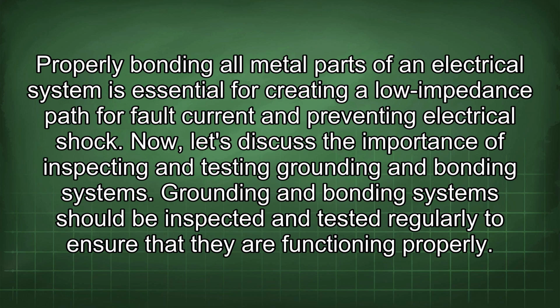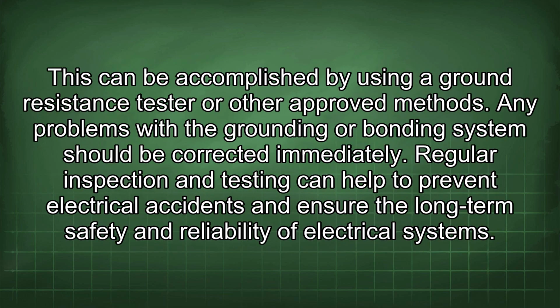Properly bonding all metal parts of an electrical system is essential for creating a low impedance path for fault current and preventing electrical shock. Now let's discuss the importance of inspecting and testing grounding and bonding systems. Grounding and bonding systems should be inspected and tested regularly to ensure that they are functioning properly. This can be accomplished by using a ground resistance tester or other approved methods. Any problems with the grounding or bonding system should be corrected immediately. Regular inspection and testing can help to prevent electrical accidents and ensure the long-term safety and reliability of electrical systems.